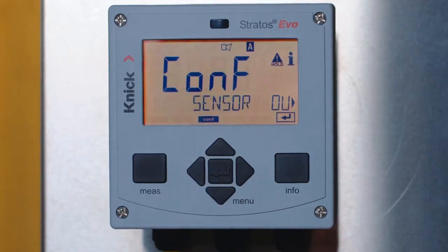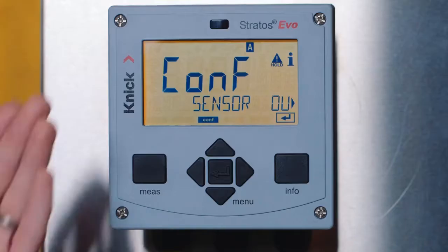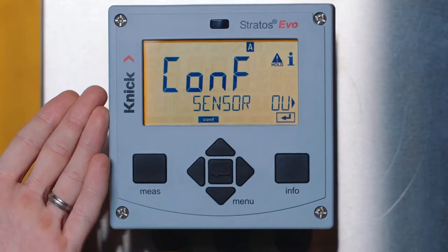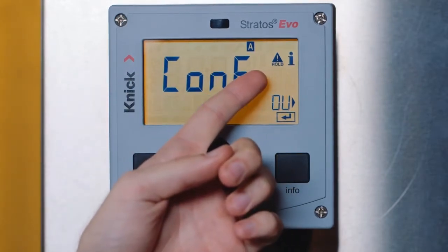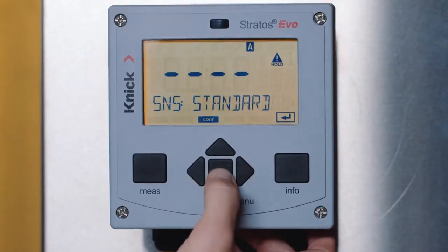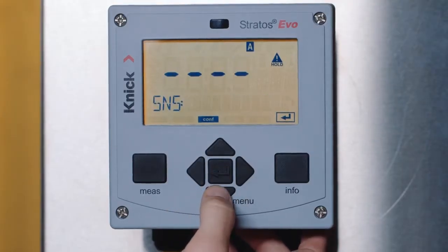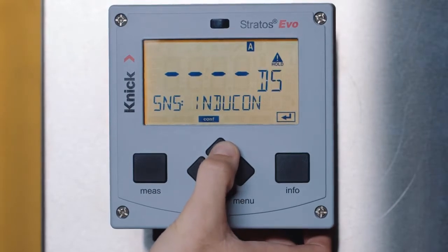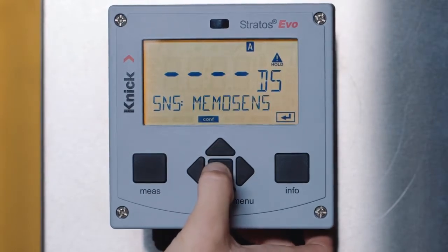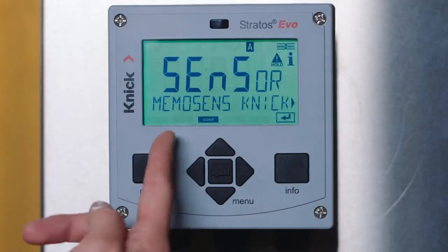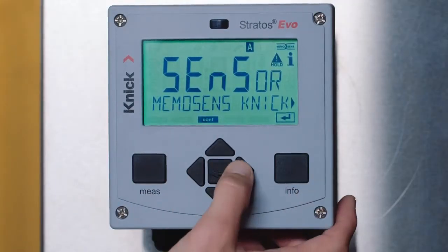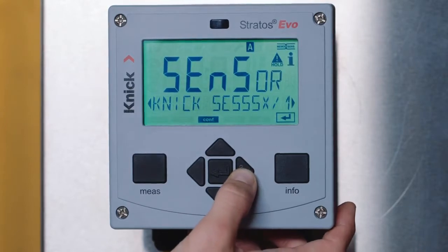You'll notice once we enter the parameter set, the transmitter enters a hold mode. This is indicated by the backlit display changing to yellow and the hold icon on the screen. Hold mode ensures that your control system does not receive erroneous values while you're configuring the transmitter. Next, press enter to select sensor. In this menu, you will choose the type of sensor that's connected. We will select Memosens and press enter. You will see that when a Memosens sensor is connected, it identifies the sensor and gives the make and model.